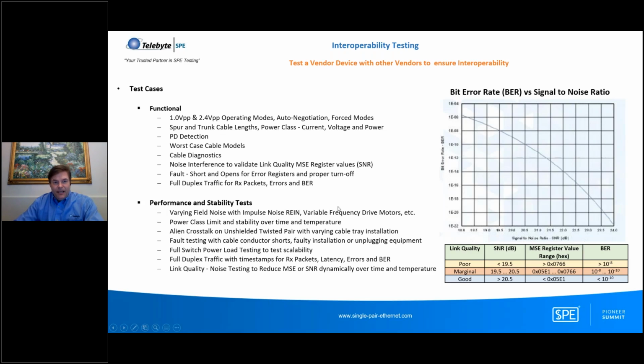And in the performance and stability tests, we want to test in varying noise environments. There is what we call impulsive noise, or repetitive electrical impulse noise. This is noise that comes from electrical equipment plugged into the electrical outlets, and it radiates impulsive noise. There are variable frequency drive motors often in plants, elevators, pulse width modulated energy efficient devices, arc welders, and robotics that can all generate impulsive noise. And if your shielding isn't installed correctly, that noise can couple into the single pair. So there are some tests that we can do over time, on either shielded or unshielded twisted pair, to test how well the data performance is going to be.